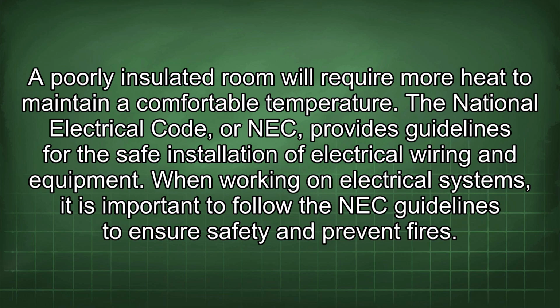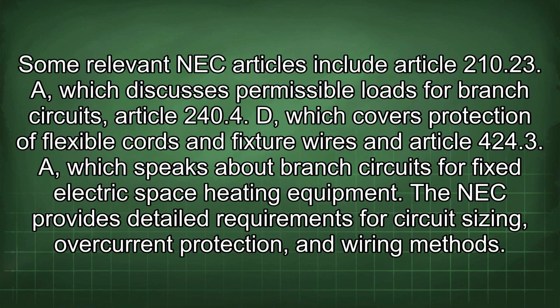The National Electrical Code, or NEC, provides guidelines for the safe installation of electrical wiring and equipment. When working on electrical systems, it is important to follow the NEC guidelines to ensure safety and prevent fires. Some relevant NEC articles include Article 210.23(A), which discusses permissible loads for branch circuits, Article 240.4(D), which covers protection of flexible cords and fixture wires, and Article 424.3(A), which speaks about branch circuits for fixed electric space heating equipment.